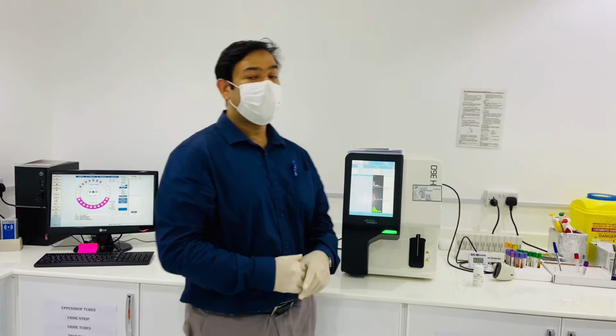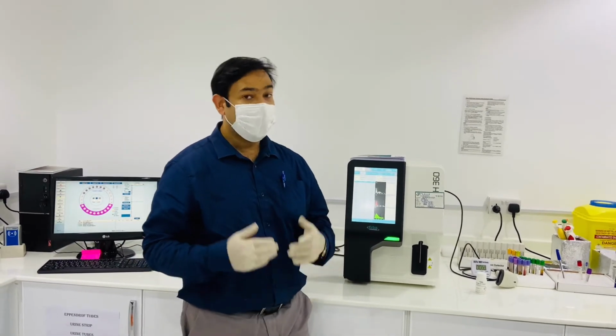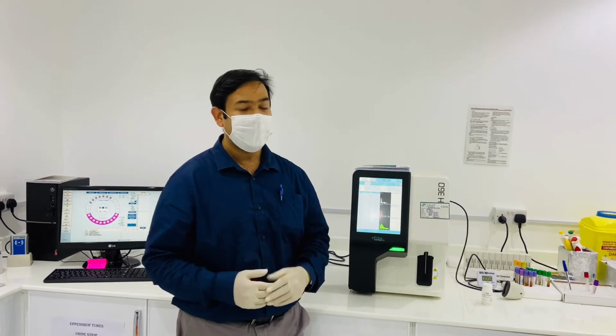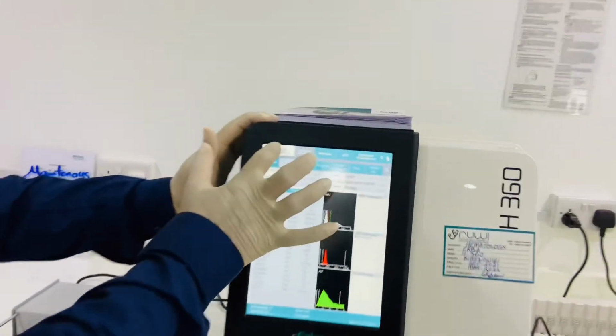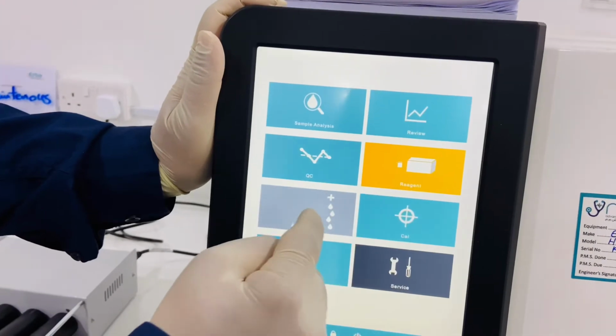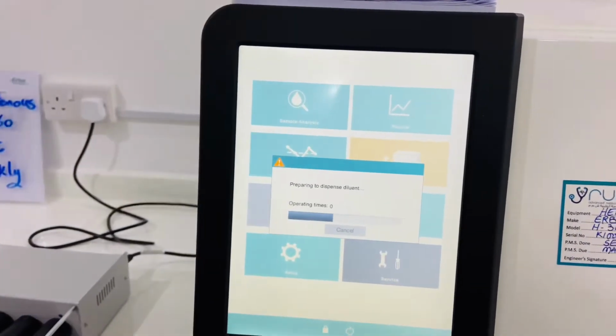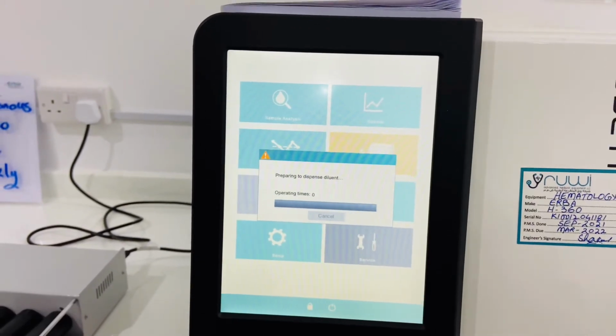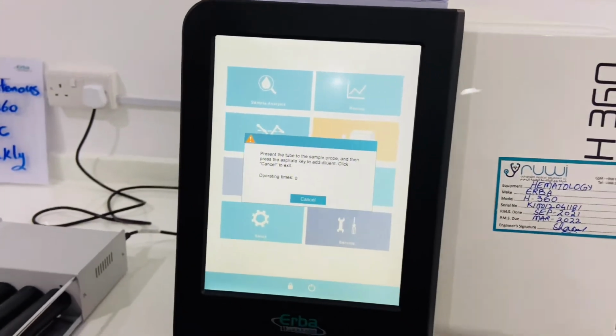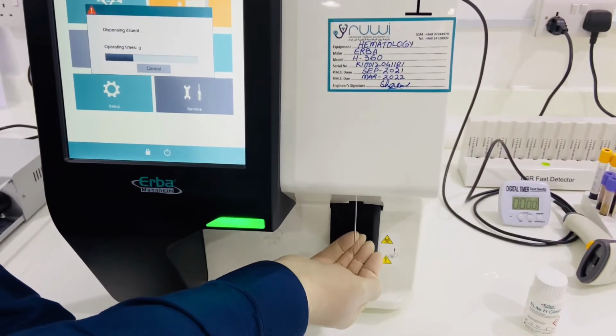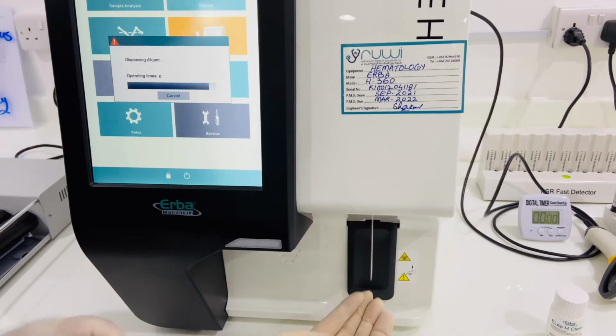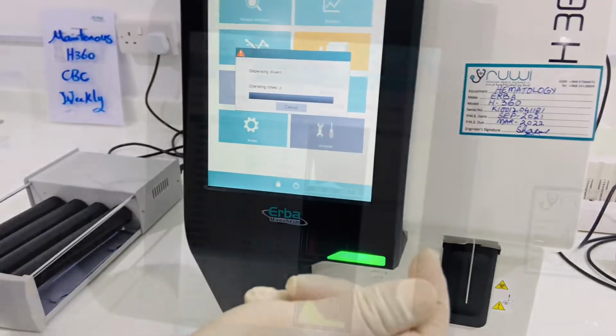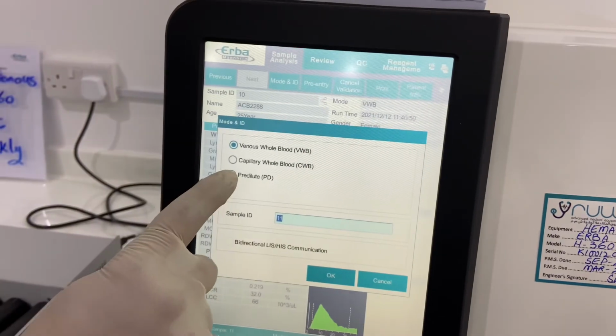So guys, now I will show you how to run the sample in pre-dilution mode. As you know, there are many machines in which you cannot run the pre-dilution mode. For the pre-dilution mode, you have to add the diluent, but in this machine there is no need to add the diluent manually. I will show you how to add the diluent to the sample. So come, I will show you. Click here. This is add diluent. Click add diluent. Now it will make it ready. So how can we collect the diluent from here? Just press the button. So you will see now I have diluent in my hand. See, I have the diluent. Now click on Mode & ID and select PD Mode.